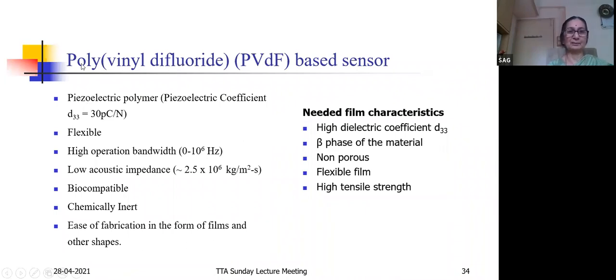We selected polyvinylidene fluoride for this particular material because it has a piezoelectric coefficient of about 30 picocoulomb per Newton. It is flexible. It has a high operation bandwidth, right from 0 to 10^6. It has low acoustic impedance, which we were requiring. It is biocompatible. If you put it on the human hand, biocompatibility is also to be seen, otherwise the person will get irritated. It is a chemically inert material, and it is easy to fabricate in the form of films and other shapes. Therefore, we selected this.